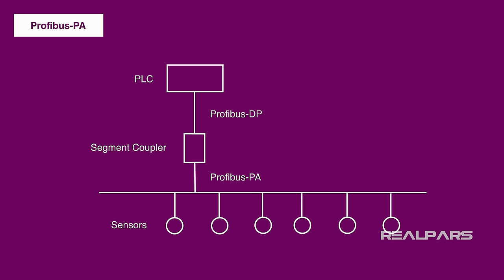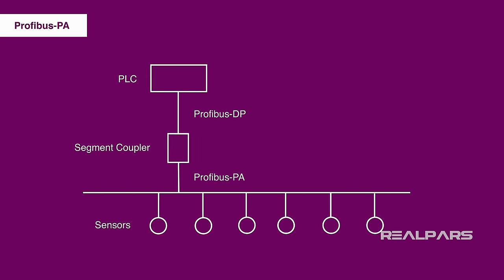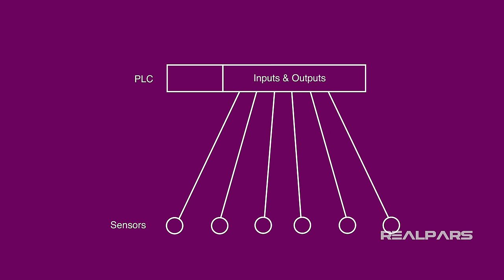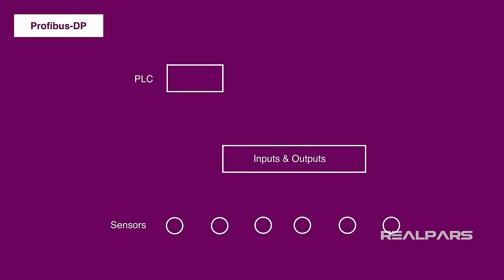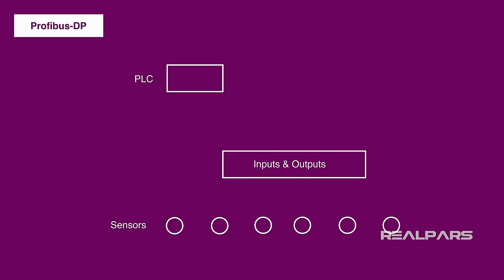So let's summarize how these two industrial communication protocols have changed the ease and efficiency of setting up PLC controls. With the invention of the Profibus DP, we were able to advance from having the PLC in the control room directly connected to the sensors on the factory floor, to decentralizing the IOs and moving them next to the sensors, and then using a simple RS-485 to connect the IOs to the PLC.